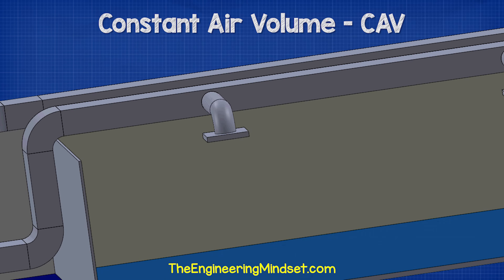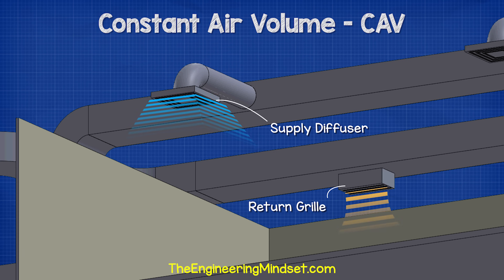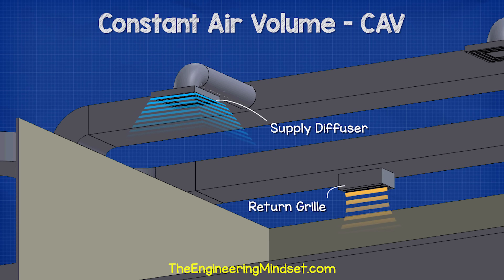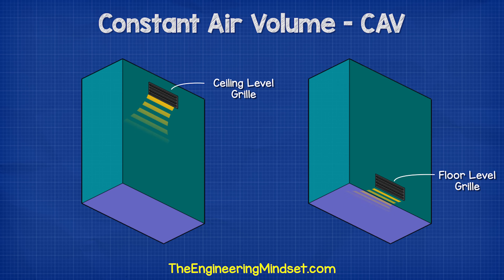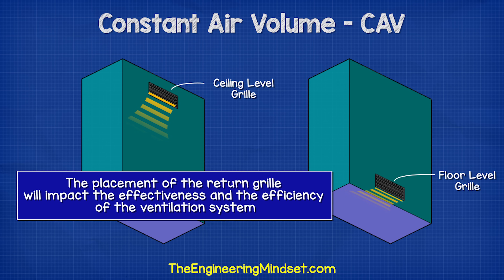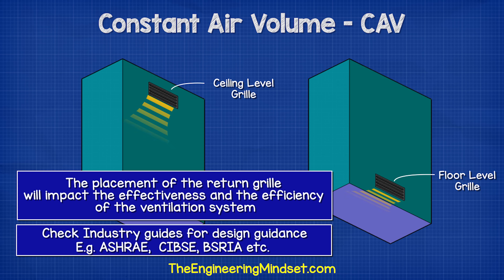The air is then circulated around the room and pushes the dirty used air into the return grille. The return grille is typically on the opposite side of the room, sometimes at floor level and sometimes at ceiling level. The placement of the return grille will impact the effectiveness as well as the efficiency of the ventilation system. Various industry bodies will provide guidance on the design of such a system.